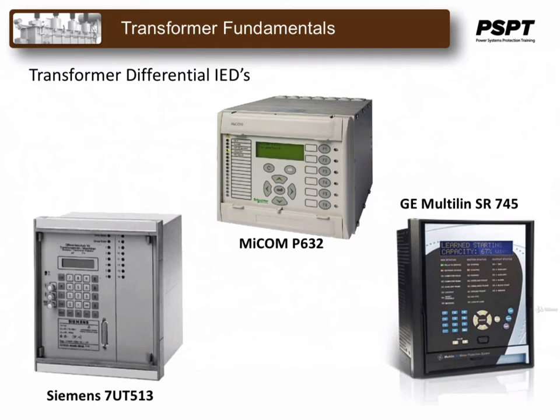Now, these are only three of a multitude of relays that are out there on the market, and certainly internationally you'll find even more. However, these are a good representation of what is out there today, and with technology changing as it does, these devices are changing very rapidly in themselves. However, if we look at these three samples, they'll give us a good idea of what IED type relays function as and what they're capable of doing out there in the way of transformer protection.